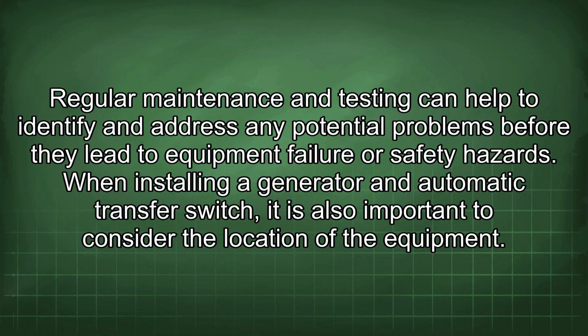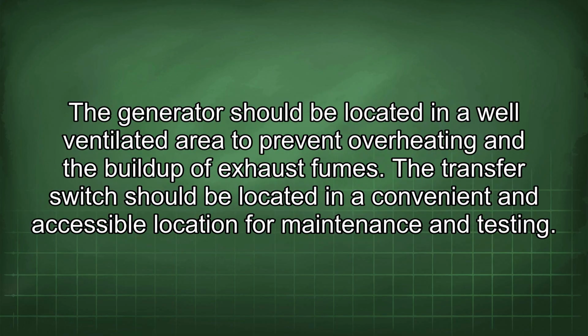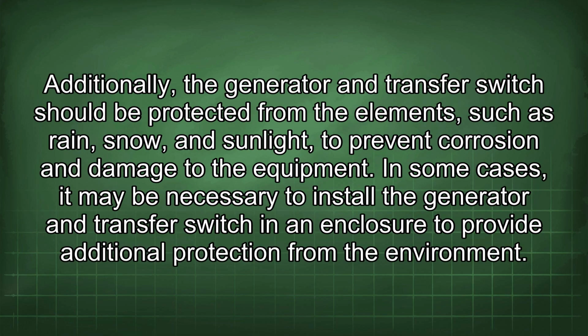When installing a generator and automatic transfer switch, it is also important to consider the location of the equipment. The generator should be located in a well-ventilated area to prevent overheating and the buildup of exhaust fumes. The transfer switch should be located in a convenient and accessible location for maintenance and testing. Additionally, the generator and transfer switch should be protected from the elements such as rain, snow, and sunlight to prevent corrosion and damage to the equipment.